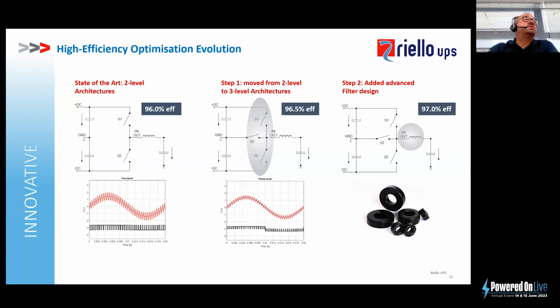The next stage, coming back to that, took us up to efficiency levels of around 96.5%. So the next stage then was the filter design. We've changed the materials that are used in our filter designs, which enabled us to push the efficiency of a UPS system up to around 97%. So we're getting somewhere, we're making progress.